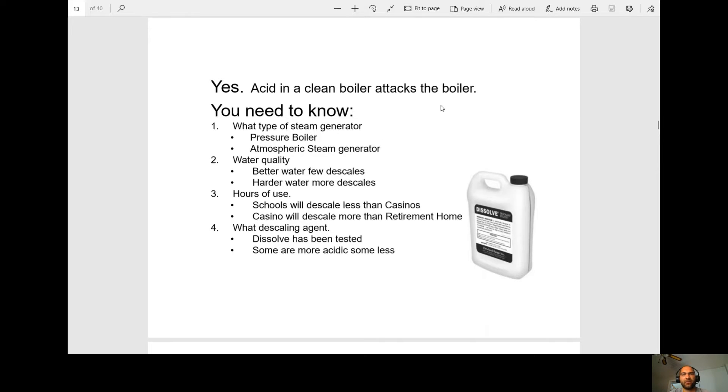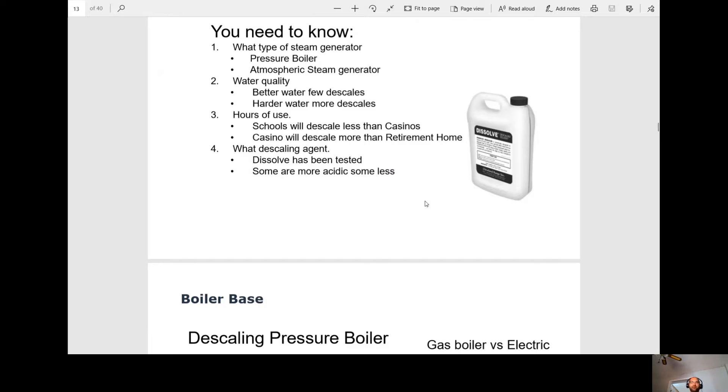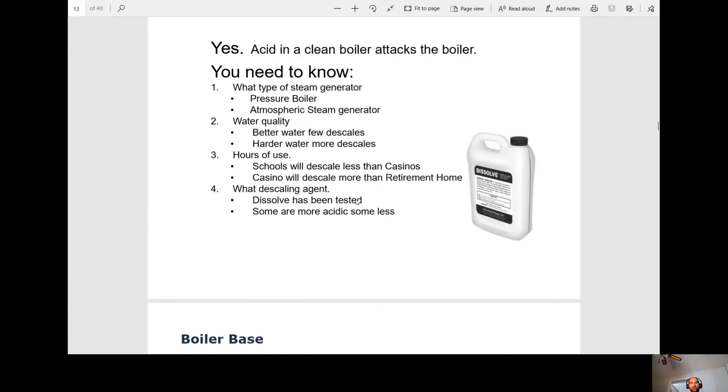So acid in a clean boiler attacks the boiler. What type of steam generators are there? There's two types, the pressure boiler and the atmospheric one. So water quality: better water means you have to descale it less often, so that's your filtration system. And the harder the water is, the more often you're going to have to descale. Hours of use: so obviously somewhere like a school, it's not being used as often, it will not have to be descaled as often. And what type of descaling agent should you use? You should be using the Dissolve. Some are more acidic, some less. That's obviously important because we don't want the acid to attack the boiler walls. So we want to make sure we use the proper product.